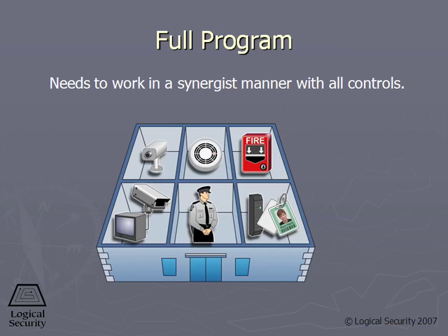In addition to fire detection, suppressants, and prevention, we also should have water detectors to identify water damage in case of a broken pipe or a sprinkler system that fails. So these can also help to minimize the amount of damage in case of some sort of water leakage. They should be placed under raised floors, placed in the drop-down ceilings. Again, very similar to smoke detectors, where do you place these? Approximately everywhere. All these things we've considered need to be put together in a cohesive plan so that they operate in a synergistic manner.